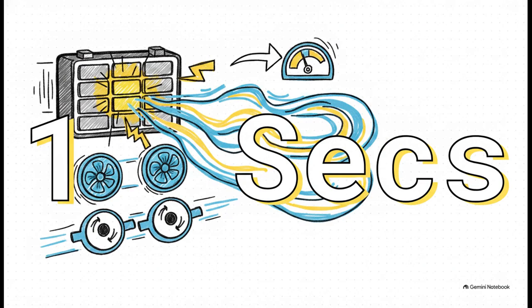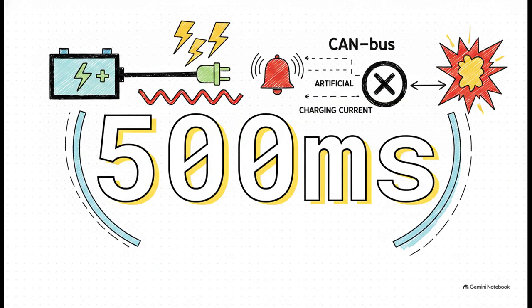Next, we have the thermal response test. Engineers will actually sabotage a battery pack by intentionally removing 30% of the cooling paste to create a hotspot. If local temperatures spike and the difference between cells exceeds 3 degrees, the software is given a mere 10 seconds of debounce time to recognize the fault. Within those 10 seconds, it has to blast the cooling pumps and fans to 100% capacity to pull that heat out.